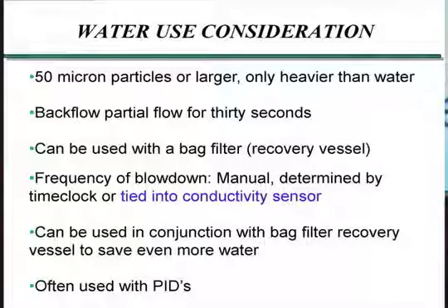And again, what we'll see is that this will be manual, tied to a time clock, or a lot of times people will tie this discharge into their conductivity sensor, which is normally controlling their bleed system anyway, so this becomes the normal location for bleed, which is kind of nice. You can kind of kill two birds with one stone. One, the regeneration of the filtration system, and two, the maintenance of bleed in the system.